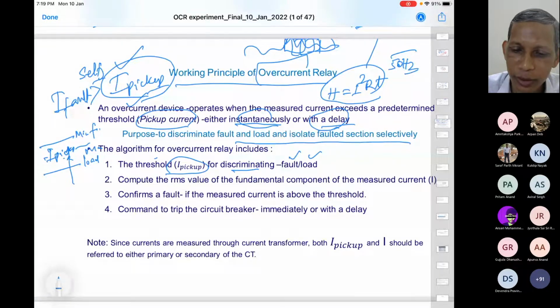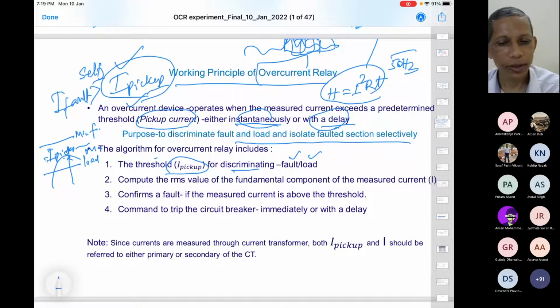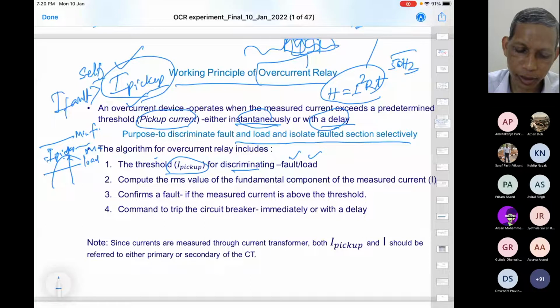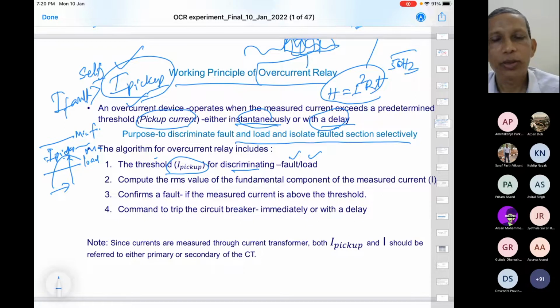Sometimes a momentary overload will happen. Suppose you are switching on a motor; sometimes momentarily the current will go above this. It should not trip, okay? Otherwise it is unnecessary tripping. Momentary load growth happens when switching on, and a large current may flow for some time, but that is not a fault. Whenever you switch on a motor, the starting current will be high. But should the protection trip?